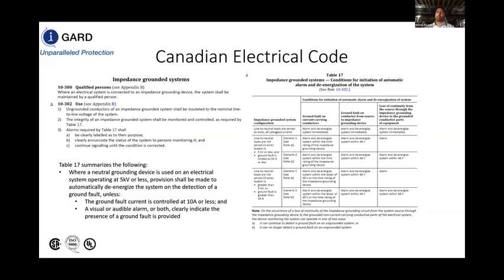3,470 watts flowing back through the neutral point up the resistor. In contrast, if we have a 13.8 kV system that also has a 10 amp NGR, that would be 80 kilowatts circulating. So typically for this section, consultants that I've been working with have been speccing out either a 10-second or 60-second rated resistor, and then tripping on first fault with coordination with their downstream feeder protection. The short circuit and open circuit scenarios for this particular row remain the same as the previous row.